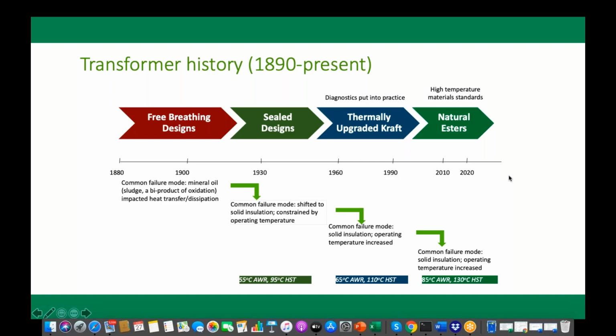What has happened over time? We went on cost engineering and the cheapest available material or the best available material, because at that time the need was to feed power to all of society. So we went on investing in mineral oils. We went on investing in other insulation materials like resins and all. And then today the product has come to a level where it is doing a great job in terms of efficiency, but it's slightly not safer. I would say slightly, because if it is maintained properly, it will work. But small negligence leads to catastrophic fires, as my friend just expressed, and we have seen a series of accidents, and I really don't want to repeat them. But today, technologies are well matured, be it dry type or liquid filled transformers, and the transformers are made fire safe. Let's get into more details further.